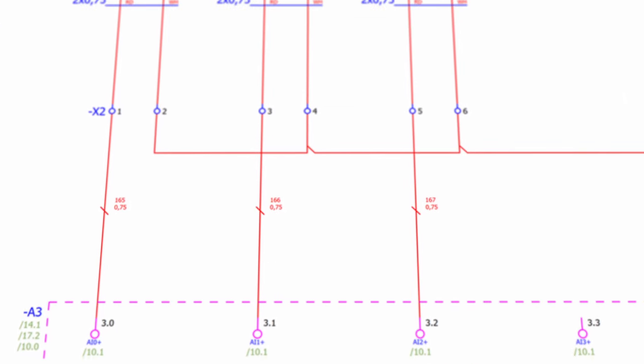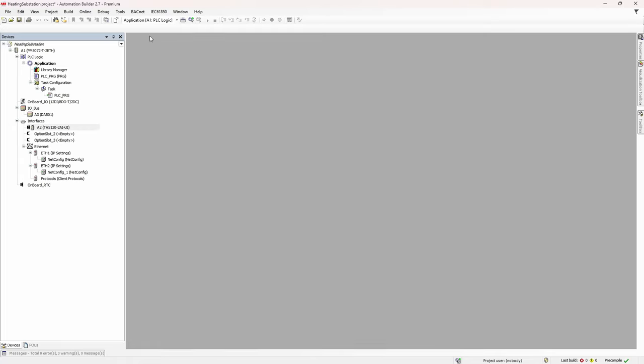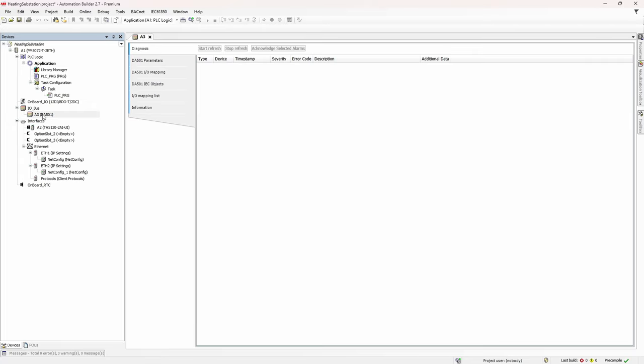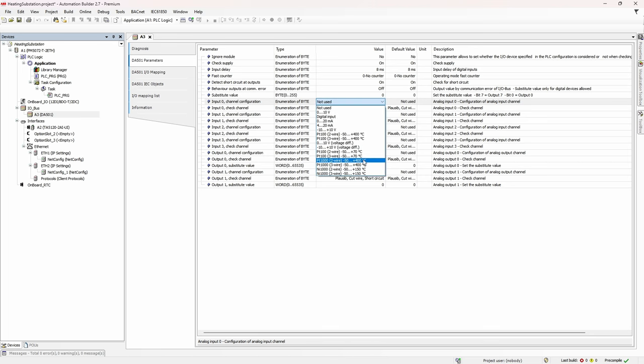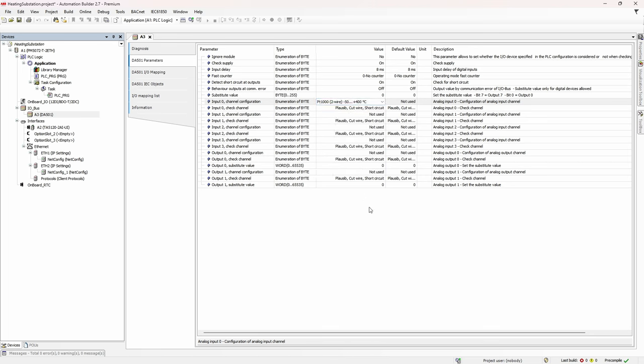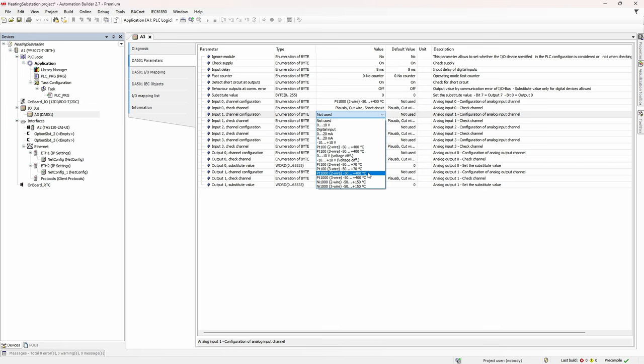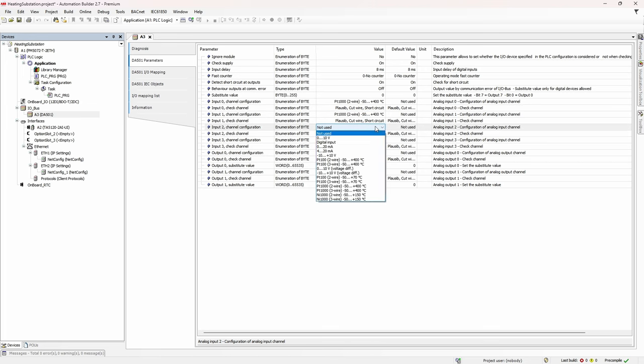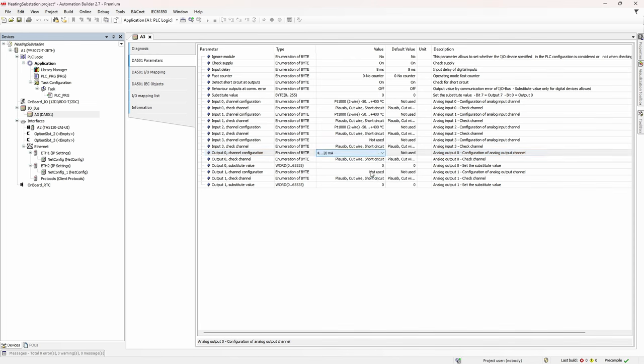And then we configure input 1 the same way. Module A3 also has IO channels, so we repeat the procedure. Go to parameters tab and change channel configuration for i0, i1, and i2 to PT1000 two wire value. Analog output 0, which is used to give speed reference to the variable speed drive, has to be configured as 4-20 mA. And that's pretty much it for IO configuration. Digital inputs and outputs, if they are not used for some special tasks like fast counting, do not require any configuration.